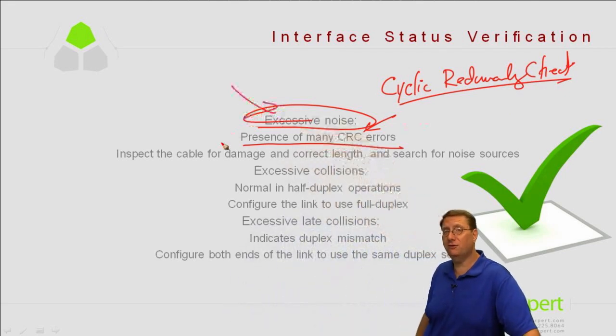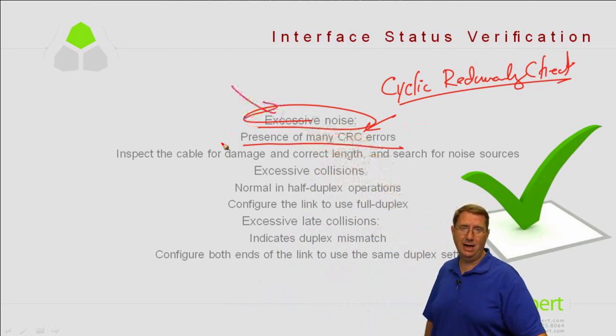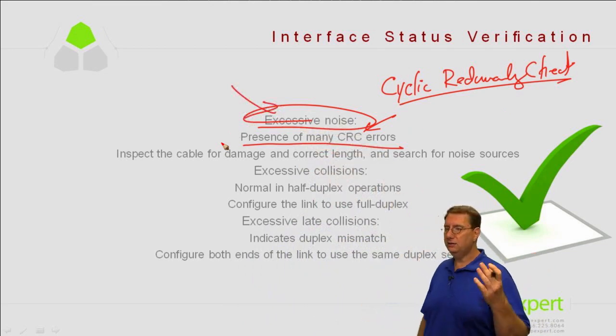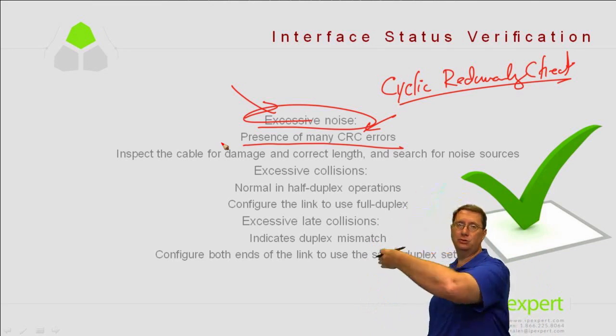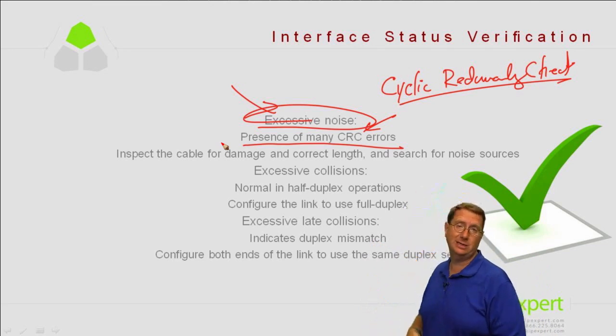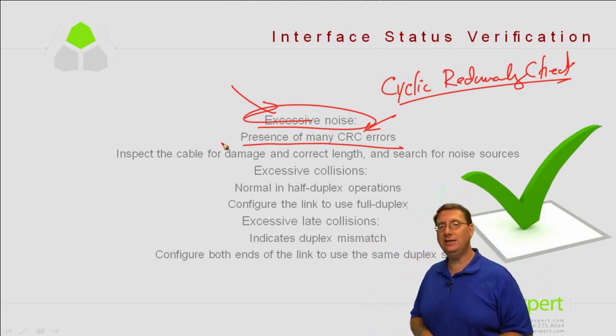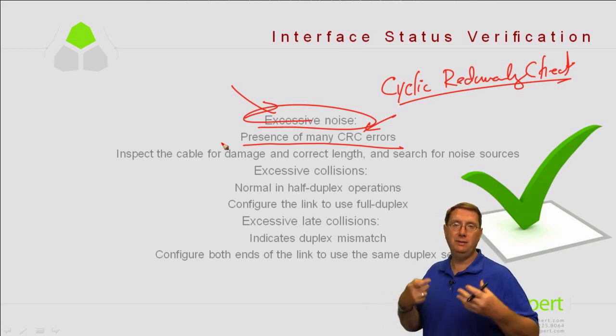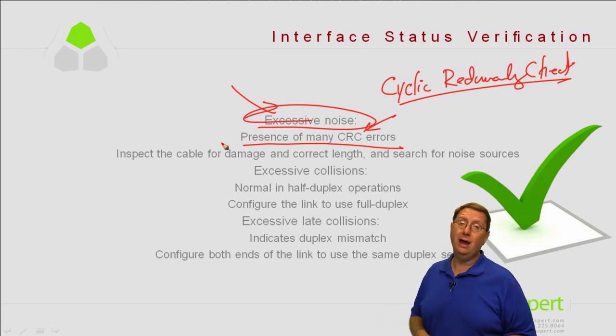That means you need to start looking for things like fluorescent light ballasts. Nine times out of ten, somebody took a shortcut and ran the cable directly over top of the can that holds the fluorescent lights. Inside that assembly is what's referred to as a ballast, a step-down transformer that steps down voltage but ups the current. The moment that happens, it becomes a radio frequency emitter, and also an EMI emitter.